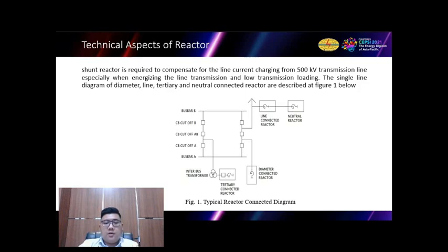Shunt reactors are required to compensate the line current charging from 500 kV transmission line, especially when energizing the line transmission and at low transmission loading. The single line diagram of diameter, line, tertiary, and neutral connected reactor are described in figure 1 below. In figure 1 below, you can see the bus bar B, CB cut off B, CB cut off AB, CB cut off A, and bus bar A. And then for the reactor, there is a tertiary connected reactor connected to the tertiary bushing of the interbus transformer, located between the CB cut off AB and CB cut off A. And for the line connected reactor, located between CB cut off AB and CB cut off B in another diameter.